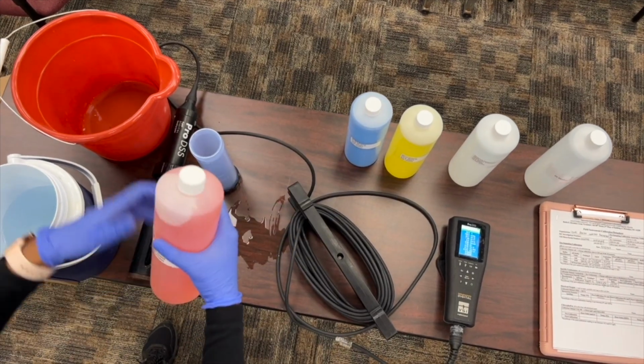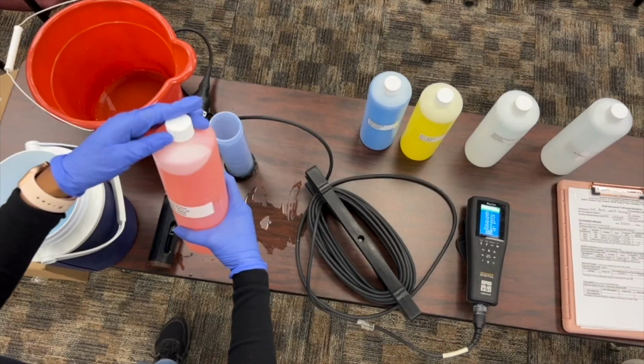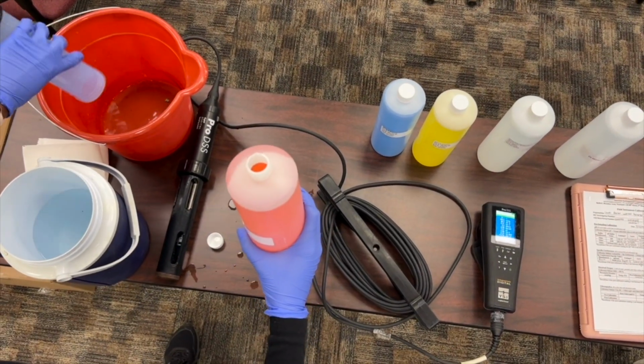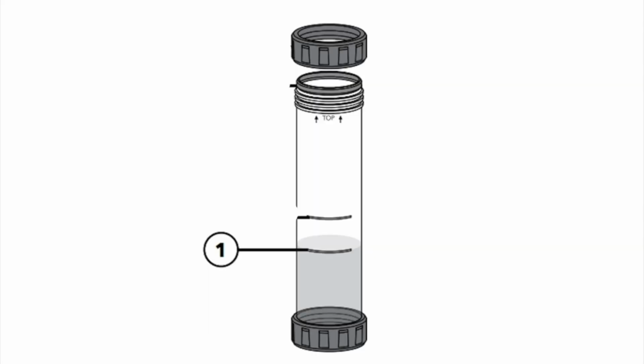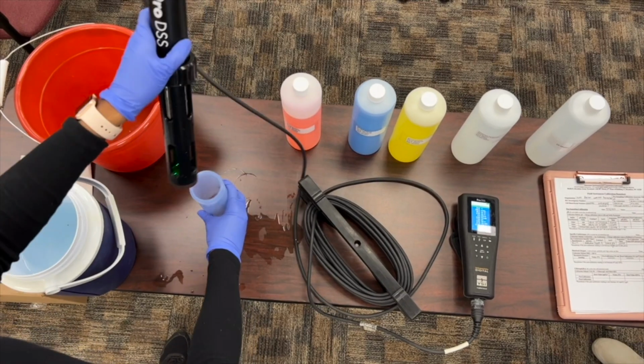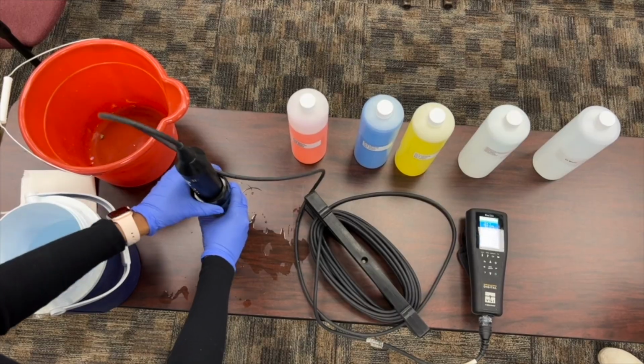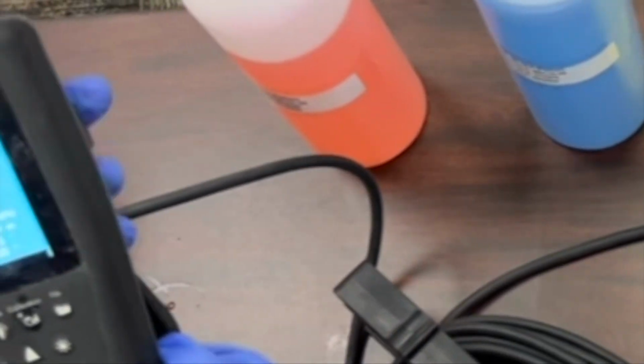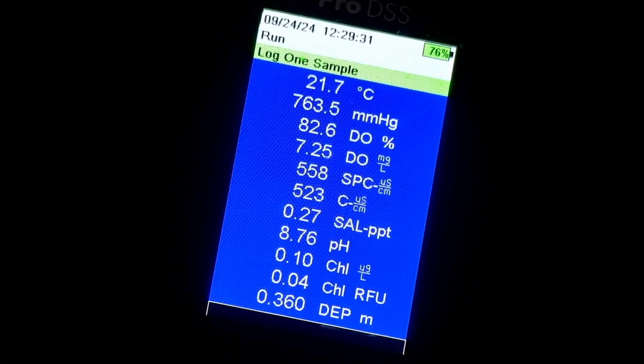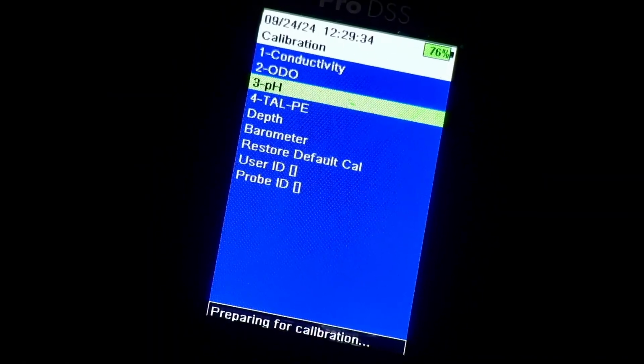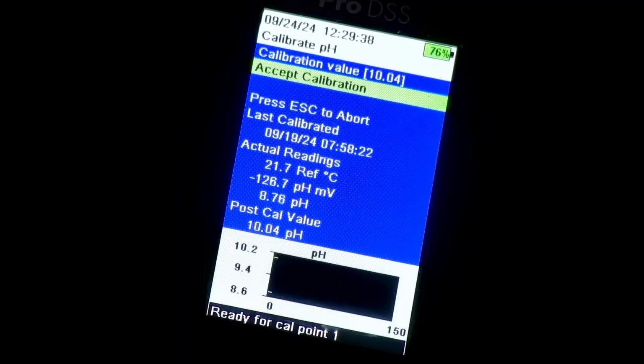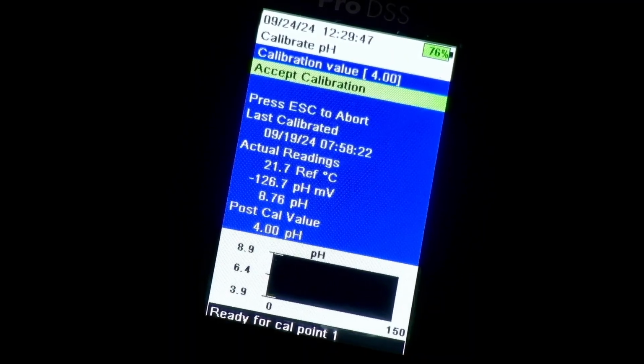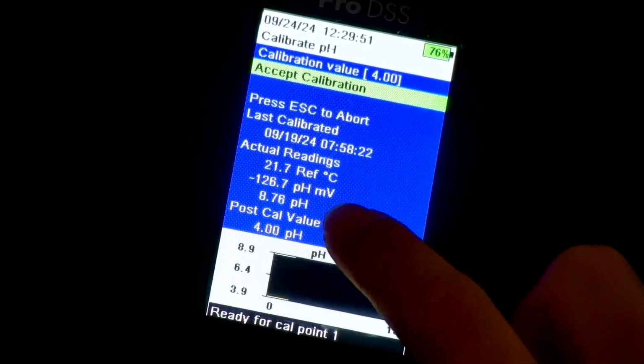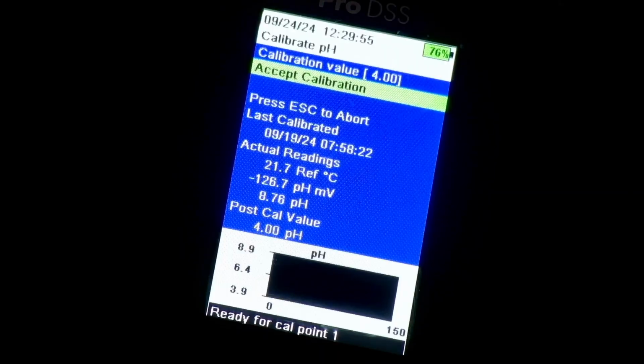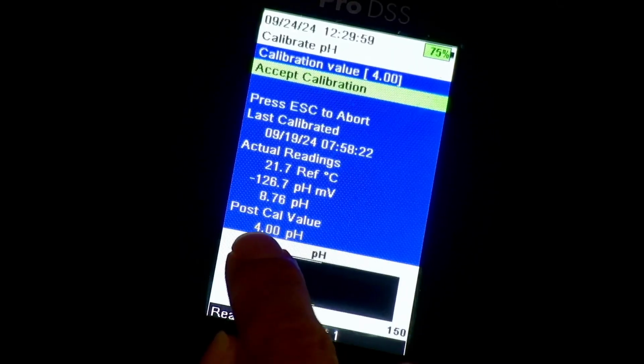We begin pH calibration using the red buffer for pH 4 to calibrate for acidic conditions. To start, fill the calibration cup to the first line. We then insert the sonde. On the YSI, press the Cal button and select pH. Once the white line on the graph stabilizes, use the numbers under actual readings to fill out pre-calibration pH and buffer temp on the calibration sheet. Use the number under post-cal value for post-calibration pH. At this point, it should say ready for cal point 1 at the bottom of the screen.